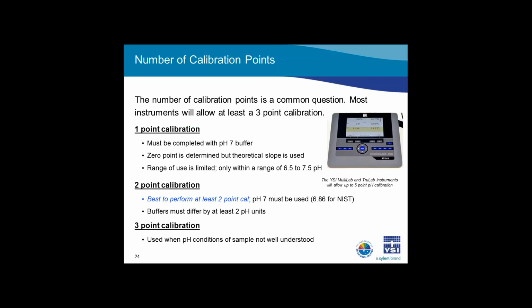The next thing to determine is the number of calibration points you want to use. You must do at least a 1-point calibration, and if you're only going to perform a 1-point calibration, make sure you're doing it with buffer 7. This will establish the intercept of the plot. However, with a 1-point calibration, a practical slope is not calculated. Instead, the meter uses the theoretical slope, which is 59.1 millivolts per pH unit. Because of this, a 1-point calibration should only be used when your expected measurement range is between 6.5 and 7.5.